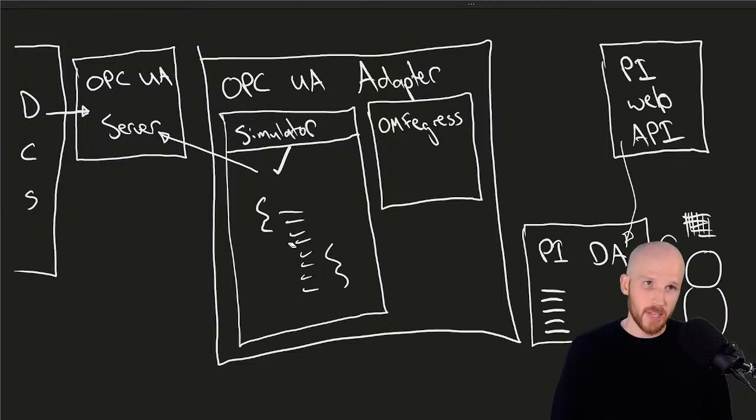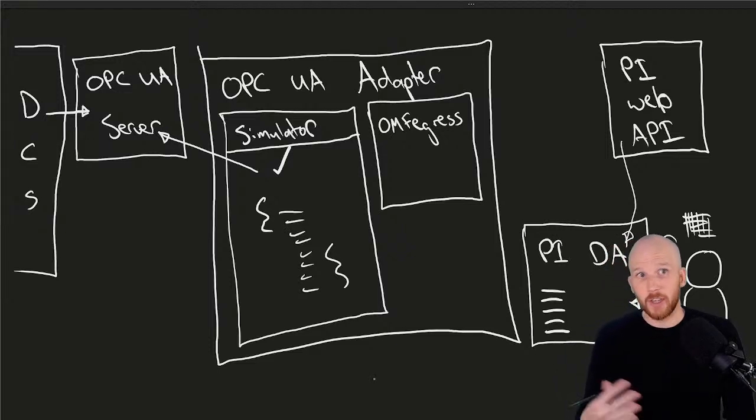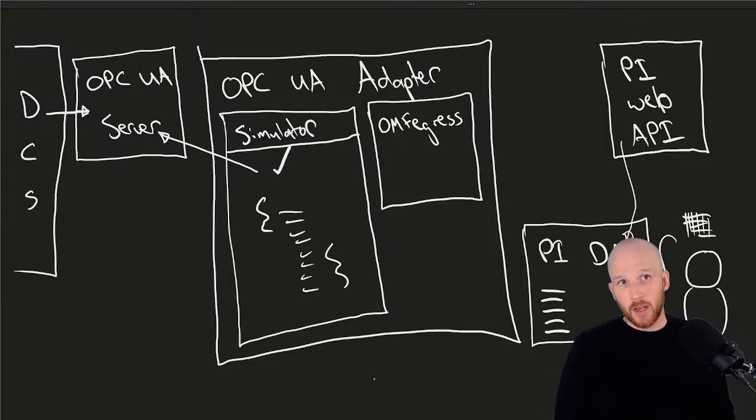So we've got this big list of tags. We're going to configure a data selection and give it this big list of tags and say, select all this data from the source and start writing it out. Now, there's a few options we have here. We can configure data filtering. Now, if you've attended the other administrator classes, data filtering is a little bit like exception in interfaces.